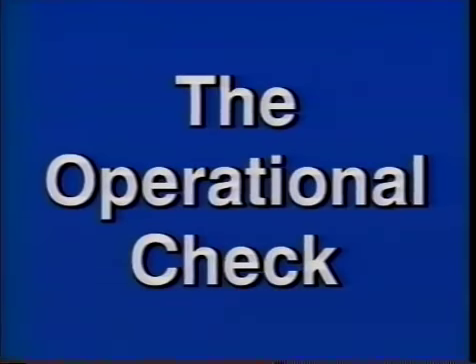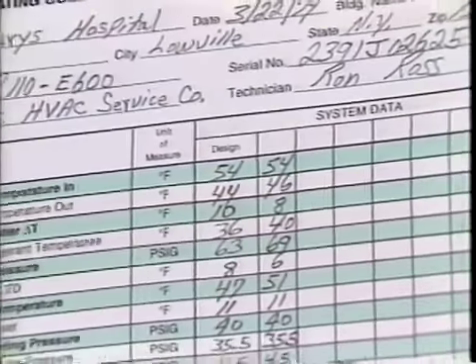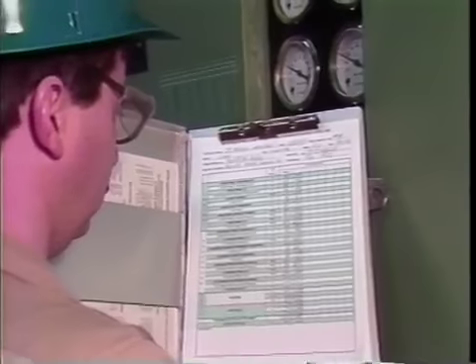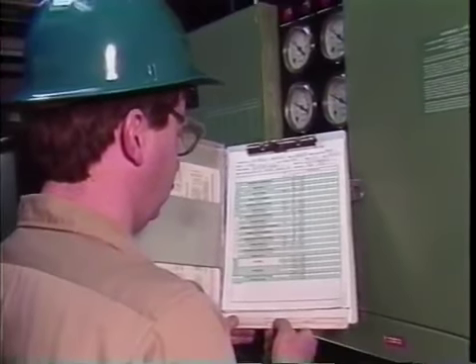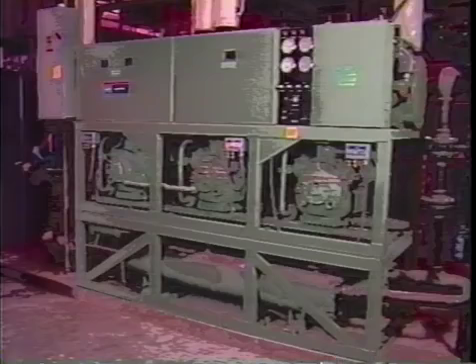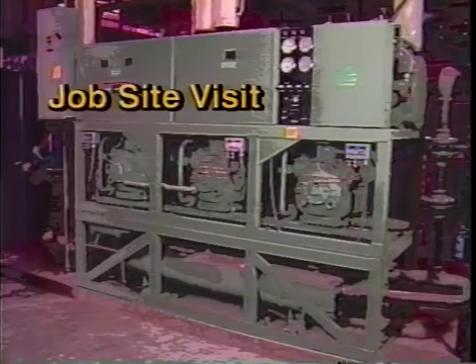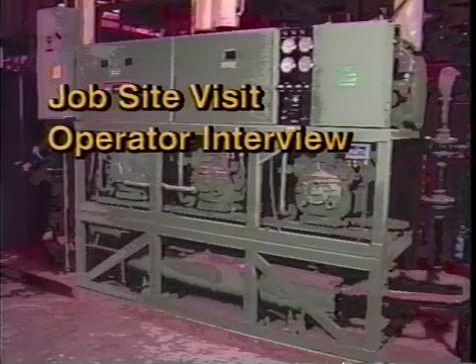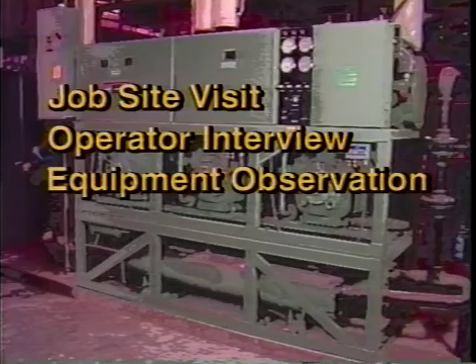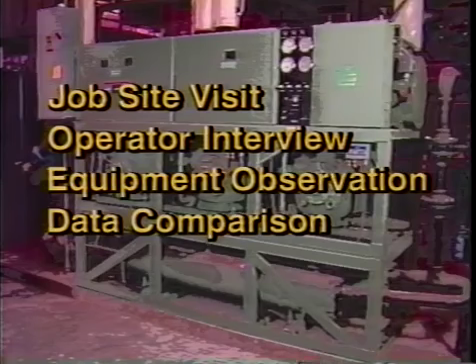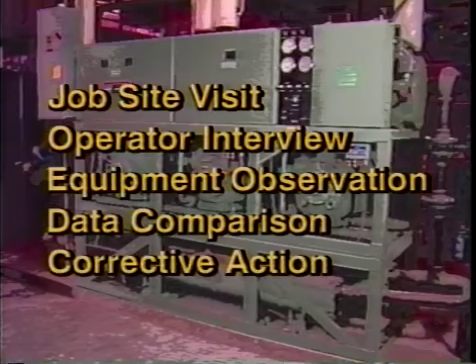Now that we have discussed some of the important topics of chiller operation, let's look at a typical operational check. The purpose of the operational check is to analyze the operation of a system so you can properly diagnose any problems. This should be done on a periodic basis so that abnormal trends can be spotted early and serious problems avoided. A typical operational check consists of a job site visit, an interview with the operator or owner, an observation of the equipment, a comparison of current operating data to both the design or initial data and also to the preceding sets of data, and correction of any faults or malfunctions.